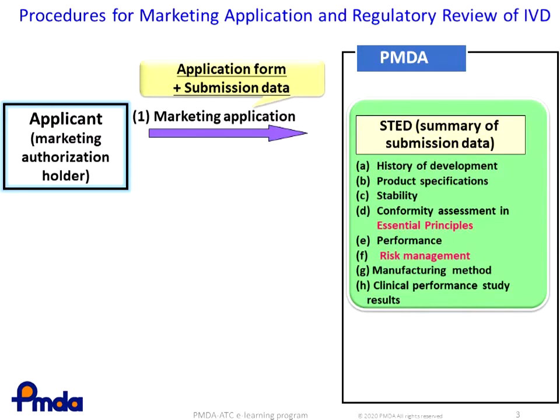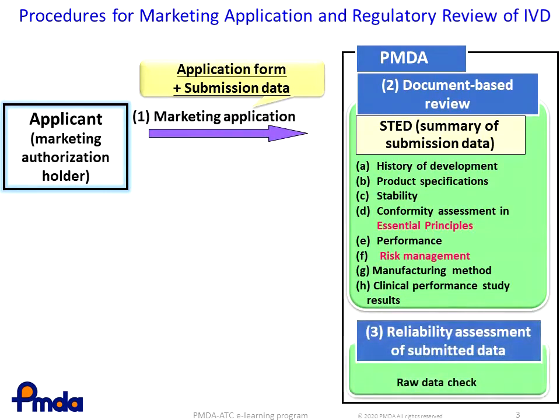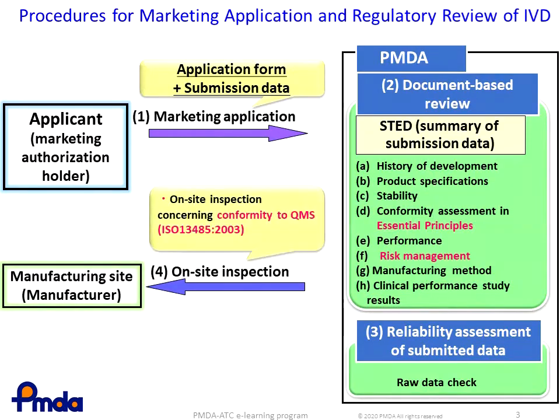The PMDA then reviews submitted documents on items such as product specifications, conformity to essential principles, performance, risk management, and so forth, to confirm the safety and performance of IVDs. The PMDA further reviews submitted raw data to assess data reliability. In parallel, an on-site QMS inspection at the manufacturing site to assess conformity to ISO 13485 will be conducted.